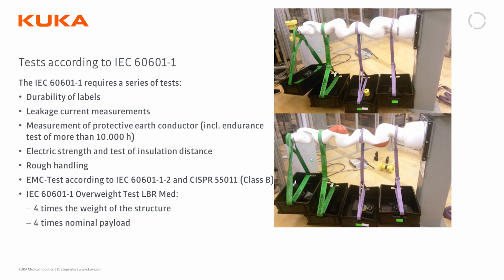In the pictures, you can see the LBR Med with additional weights attached. Those are pictures from the 4x overload test of the robot: once the 4x overload of the structure was tested, and once at 4 times the nominal payload of the robot. Other tests carried out were durability of labels, leakage current measurements, measurements of the protective earth conductor including an endurance test of 10,000 hours, as well as tests for rough handling, electric strength, and tests of the insulation distance.